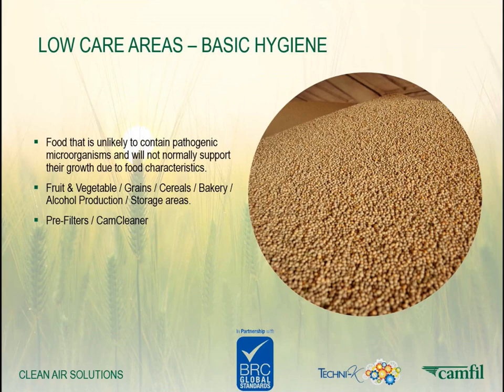Low care areas, basic hygiene areas: food that is unlikely to contain pathogenic microorganisms and will not support their growth due to food characteristics. Examples of this would be fruit and vegetables, grains, cereals, bakeries, alcohol production, and storage areas. Pre-filters, or first stage filtration, consist of filters that are classified ePM coarse. These filters, along with CamCleaner, will provide sufficient protection for low care areas. Coarse filters come in a range of bag and panel box filters and with a range of efficiencies available depending on your risk assessment needs.